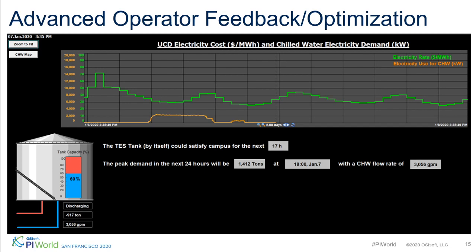I've mentioned we have these large electric chillers that use electricity to make chilled water. We have 8 of them, and they each use about a megawatt of electricity. To give perspective, our campus in the day is using about 40 megawatts, and at night about 20. So these 8 chillers are a significantly large percentage of our total electricity. You can see on the real-time data for the campus when these chillers go on and off. And then we also have a large 5 million gallon tank that allows us to store the cold water as desired, up to the capacity of the tank.